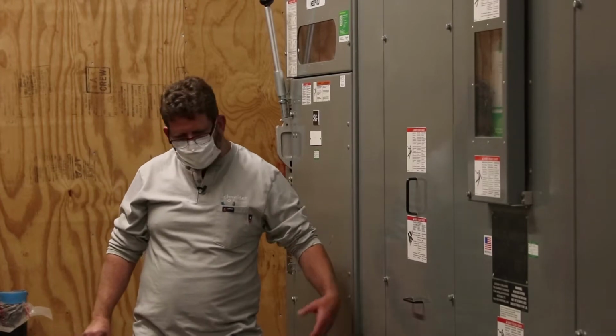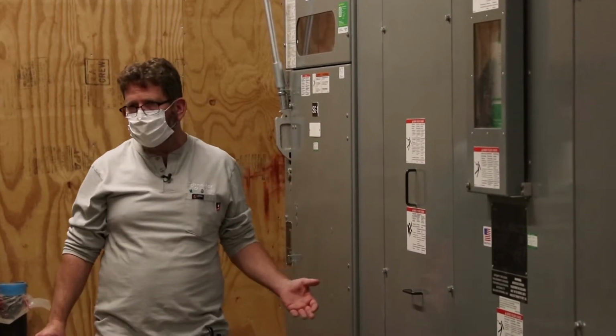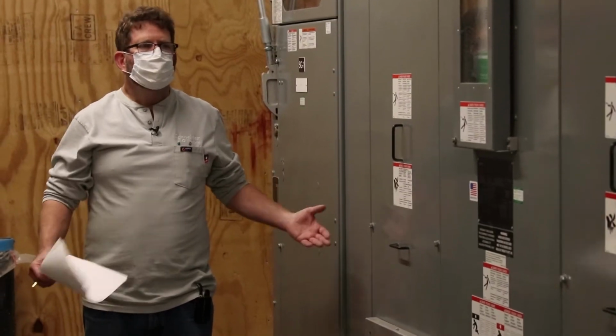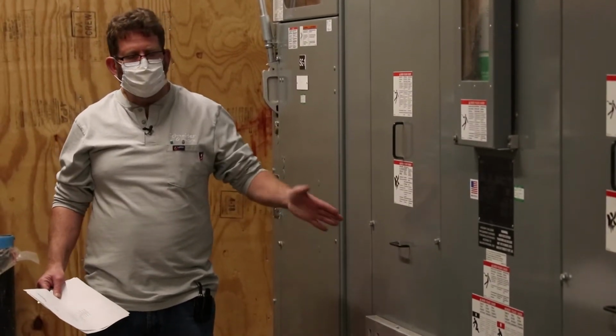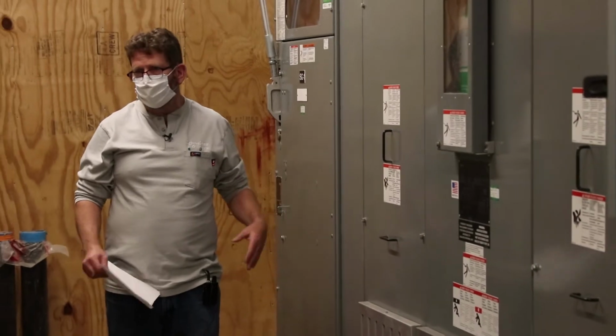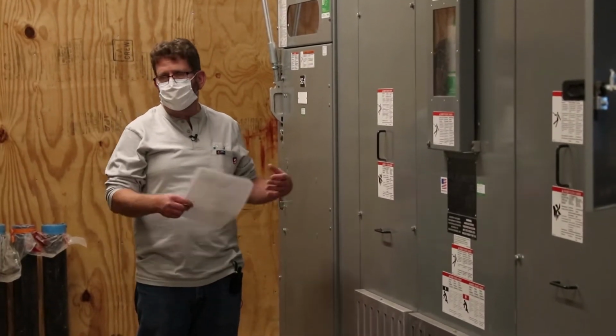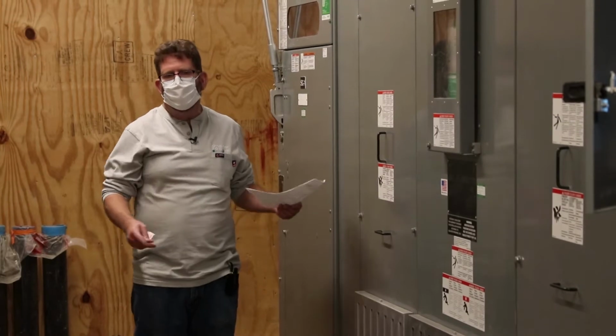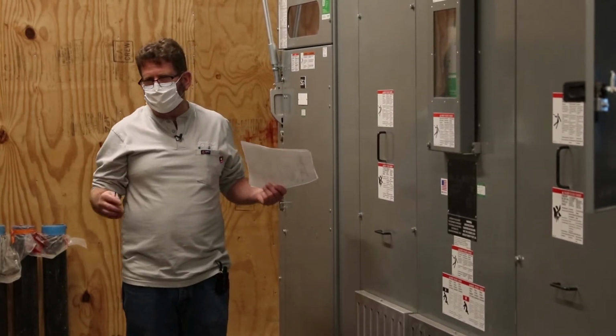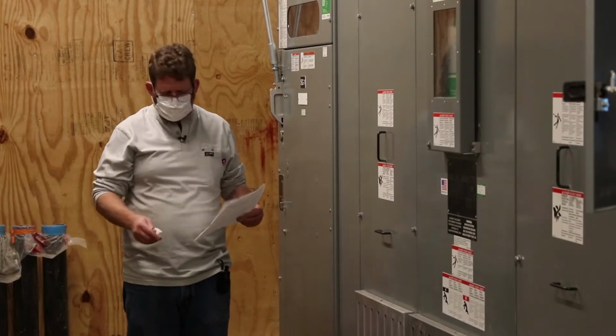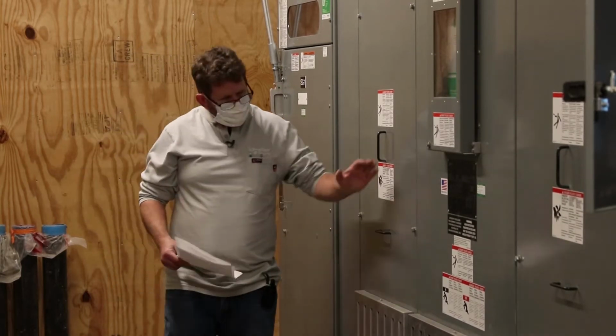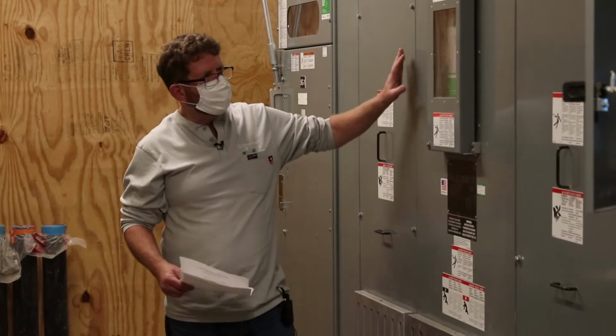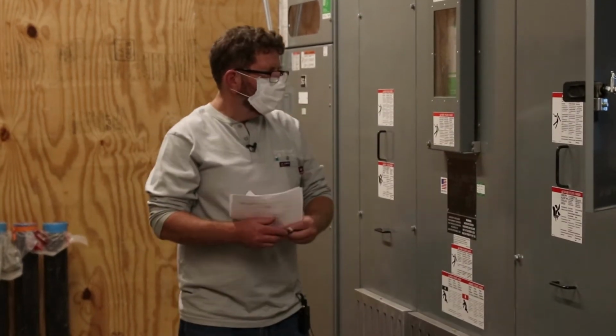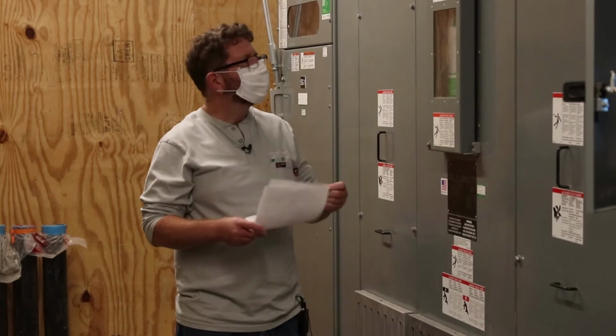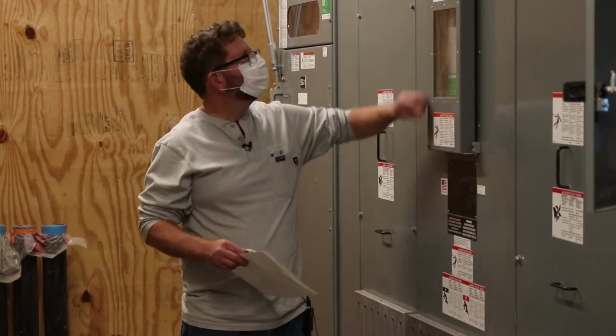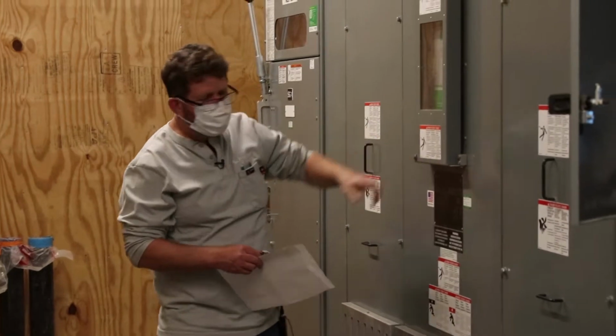So you're going to have 3 cable connections off the bottom of the switch coming in here. They're 5 kV rated cable. They're non-shielded. If you look in there, those cables should always be about 4 or 5 inches apart. They are fully insulated, but any medium voltage non-shielded cable needs to maintain 4 to 5 inch clearance between phase to phase or phase to ground. Cable will come up here into the coils. You're going to have 3 coils. This is just a dry transformer. Dry transformers.